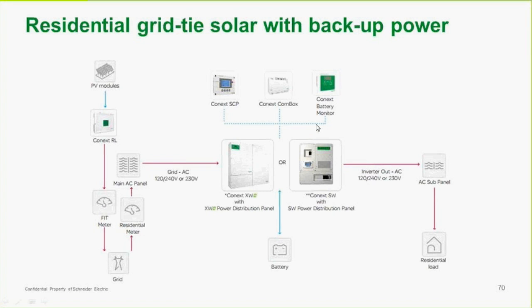The backup system is completely separate, so we still have the main panel. We have that meter coming back in from the grid to the main panel, and then it's the same setup as we previously discussed. This particular diagram does show the Conext XW or the XW Plus. They can both be used in this kind of configuration.